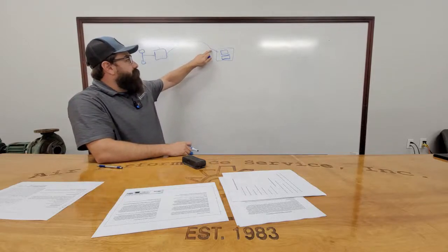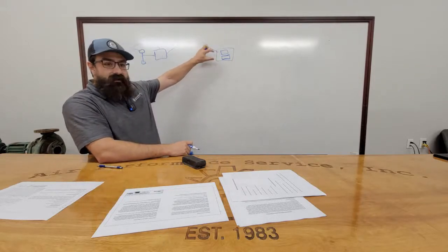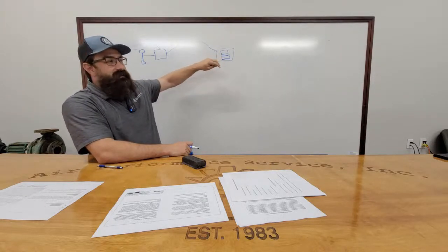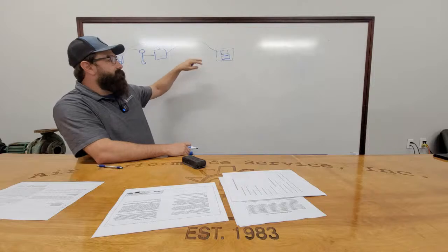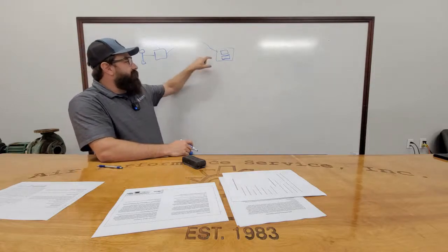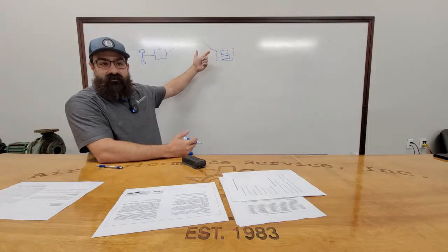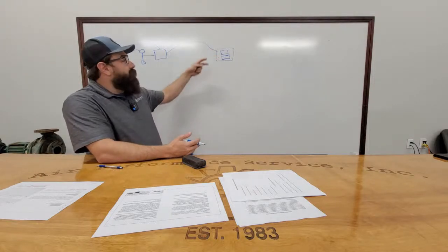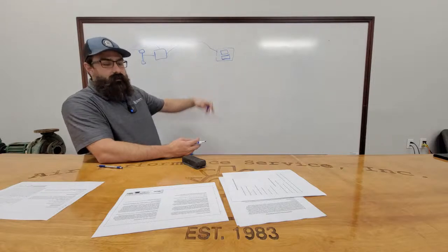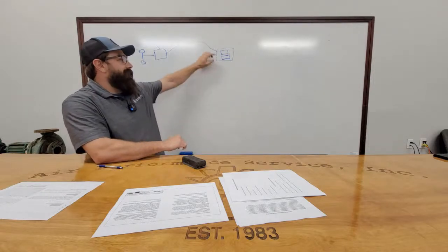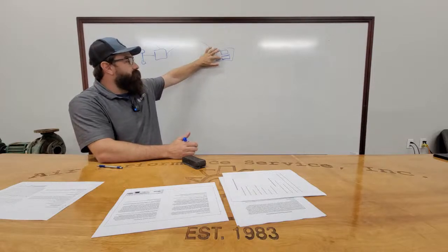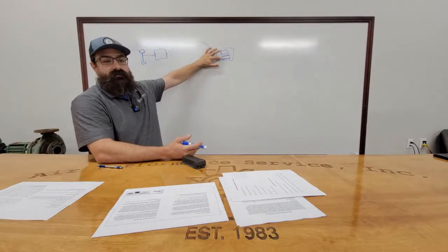If we don't have an initial delay on startup, it would instantly fire up both chillers, because let's say we're lagging based on return temp. As soon as those pumps turn on and the system's enabled, they see a return temp of 75 degrees because the system stagnated overnight. Oh, I need both chillers. Well, in reality, you don't, because you have a false load. So you would wait like an hour, 45 minutes, whatever, depending on the system, before you would start the second chiller on initial startup.